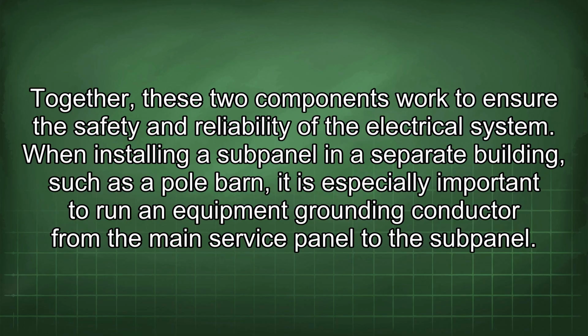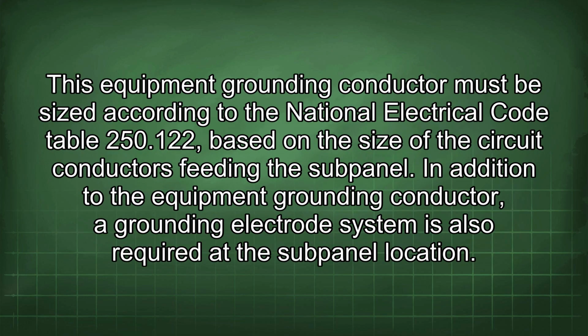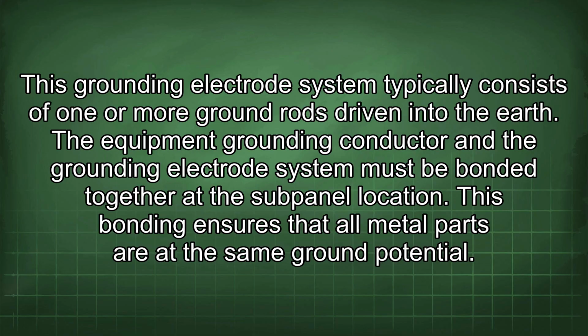When installing a subpanel in a separate building, such as a pole barn, it is especially important to run an equipment grounding conductor from the main service panel to the subpanel. This equipment grounding conductor must be sized according to the National Electrical Code Table 250.122, based on the size of the circuit conductors feeding the subpanel. In addition to the equipment grounding conductor, a grounding electrode system is also required at the subpanel location. This grounding electrode system typically consists of one or more ground rods driven into the earth.